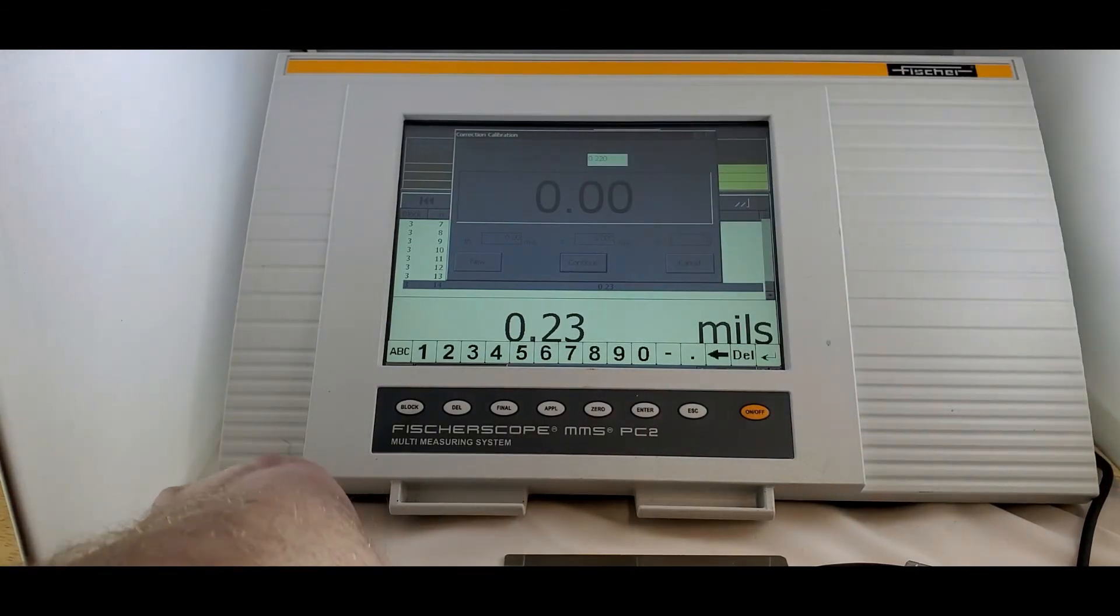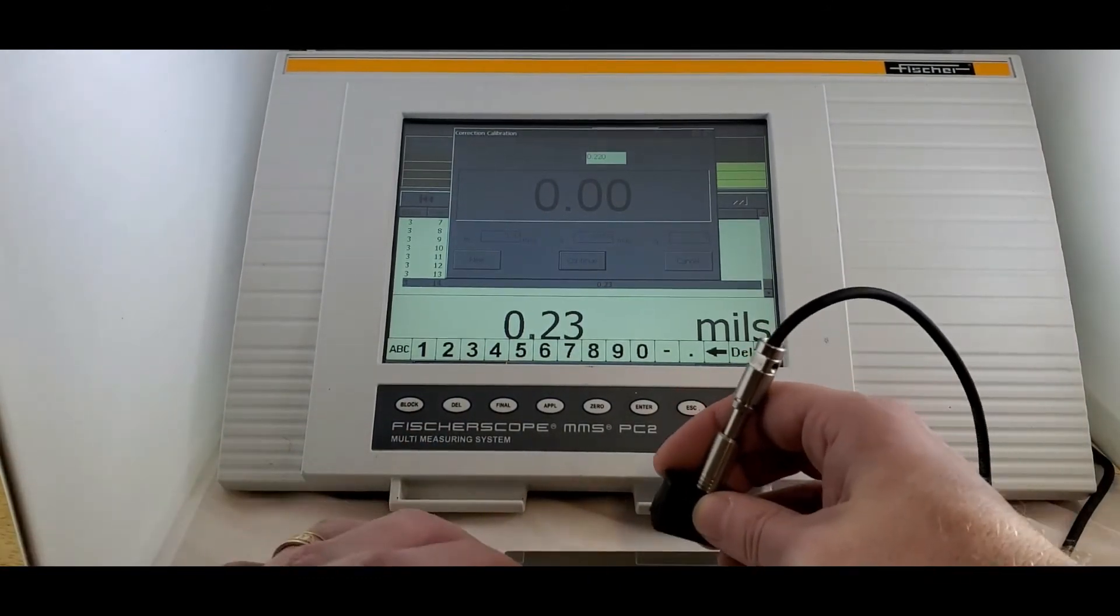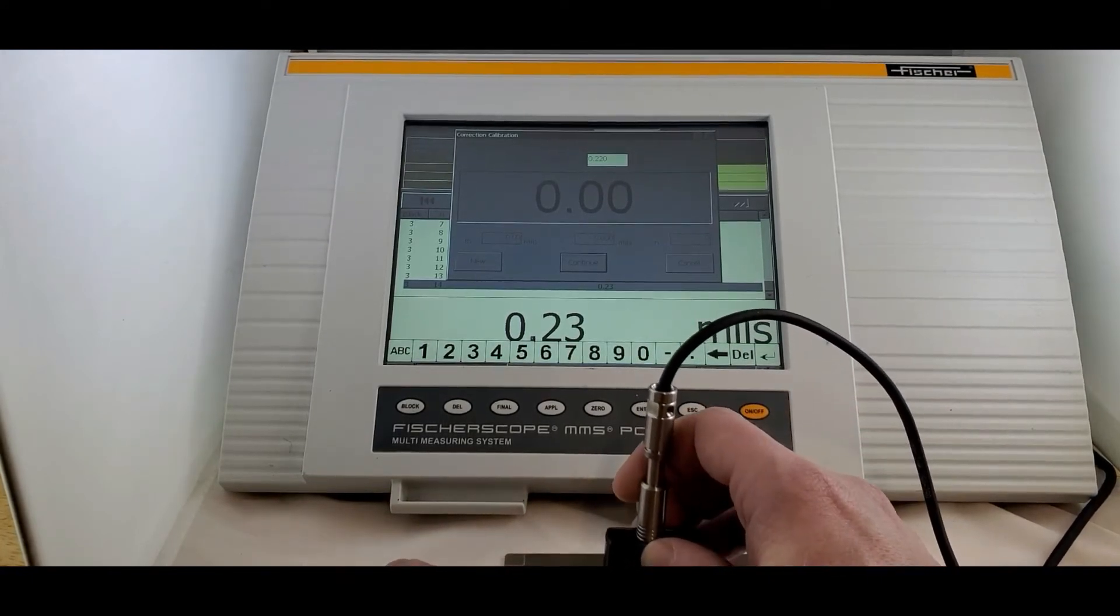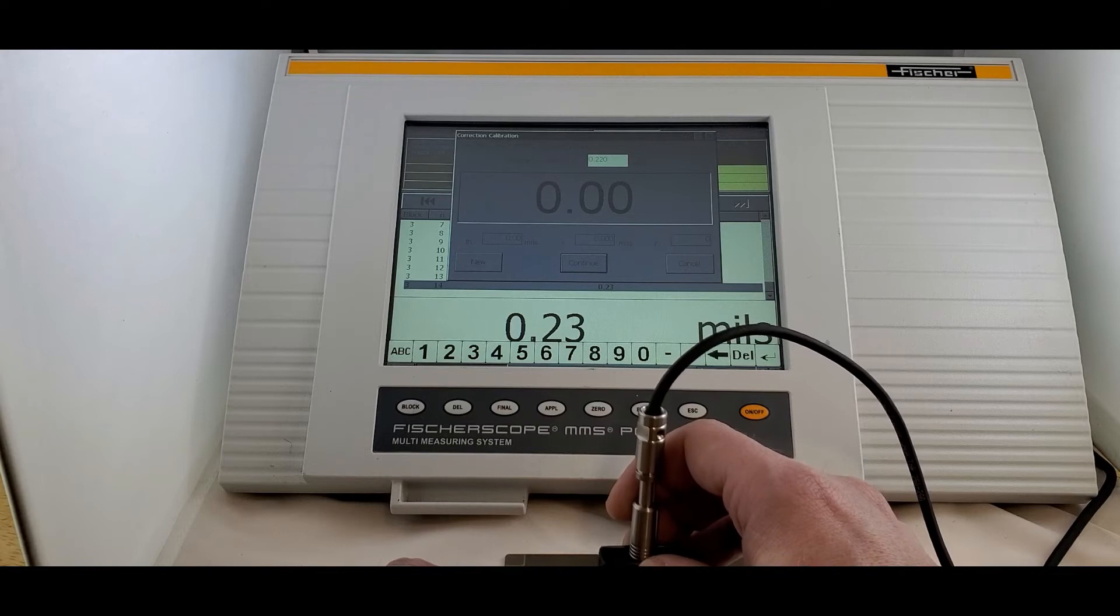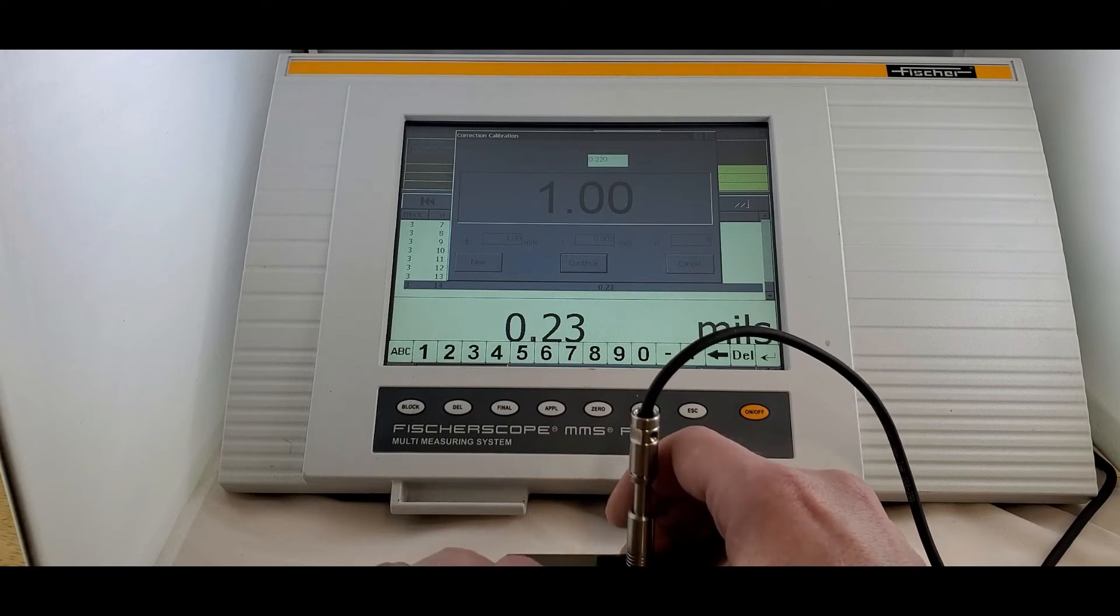So the first standard is going to be our low standard. You could do the high standard, but just to make sure that we do everything in the right order and get everything in correctly, I like to work from low to high. So again, we're going to take five measurements. One, two, three, four, five.